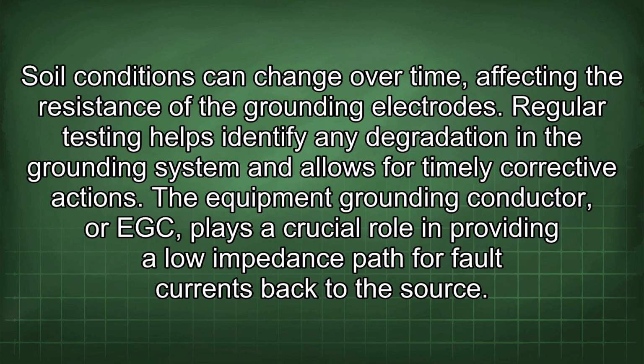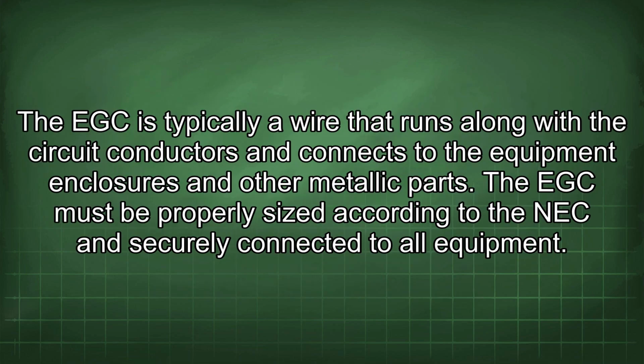Soil conditions can change over time, affecting the resistance of the grounding electrodes. Regular testing helps identify any degradation in the grounding system and allows for timely corrective actions. The equipment grounding conductor, or EGC, plays a crucial role in providing a low impedance path for fault currents back to the source. The EGC is typically a wire that runs along with the circuit conductors and connects to the equipment enclosures and other metallic parts.